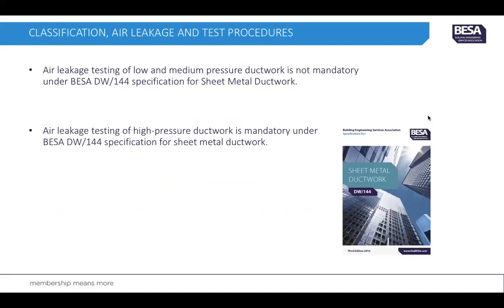Regarding classification of air leakage and test procedures: testing of low and medium pressure ductwork is not mandatory under the HVCA DW144 specification for sheet metal ductwork. However, air leakage testing for high pressure ductwork is mandatory under the HVCA DW144 specification.